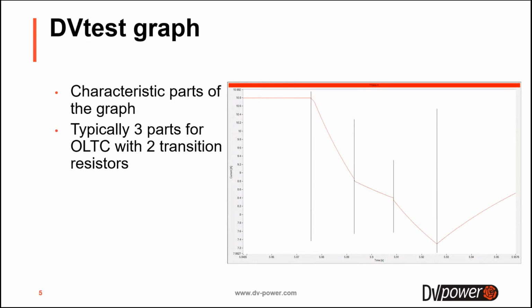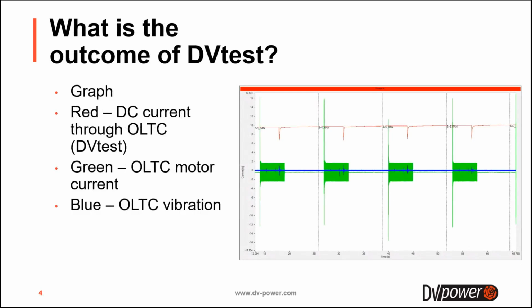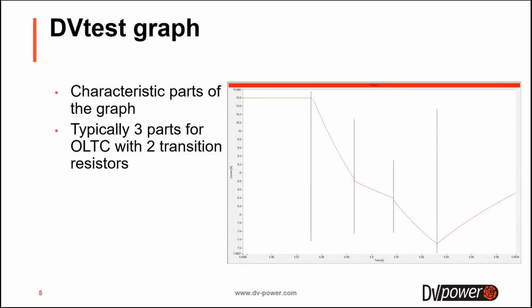Now, if we zoom in on this red part on this slide, you can see four transitions. So you can see 4 drops of current on the red part of the graph. Each of those represents one transition. The first one is the transition from tap number 2 to 3, then from tap 3 to 4, and so on. If we zoom in on one of these, we get something like this. Each graph of a transition has some characteristic parts.